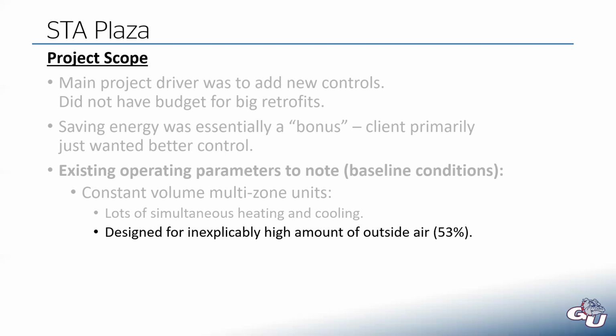If we were doing this design from scratch, we didn't do the calculation, but I suspect it would be closer to 25 to 30%. So probably half of what they were actually providing. And we talked to the client, and they couldn't think of any good reason why they were bringing in so much outside air into this building, which we know takes a lot of energy to condition.